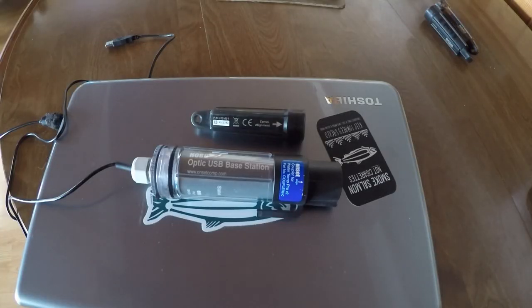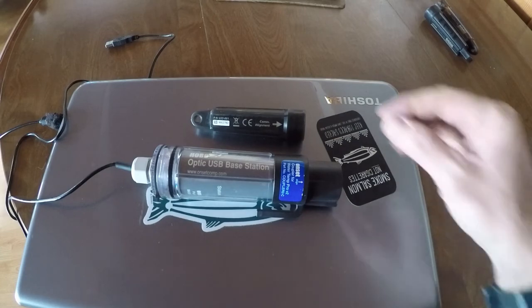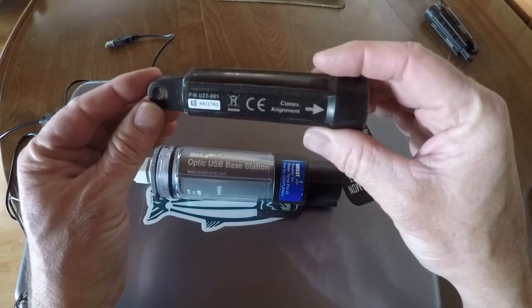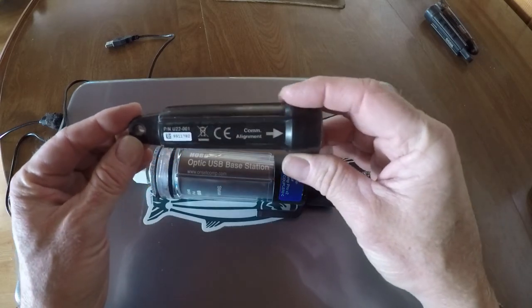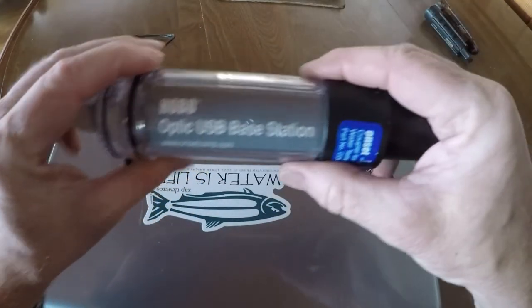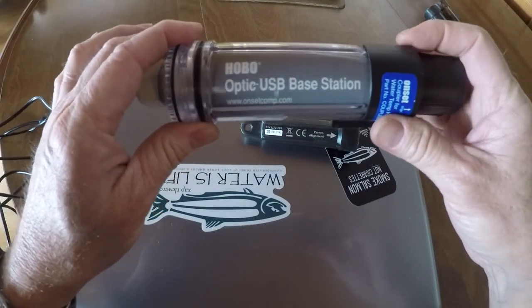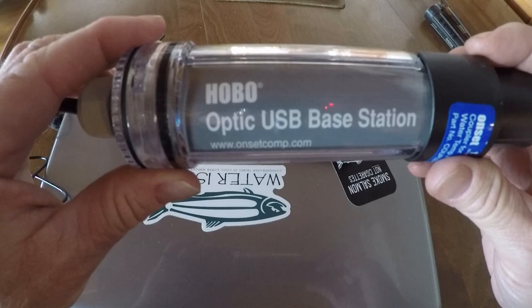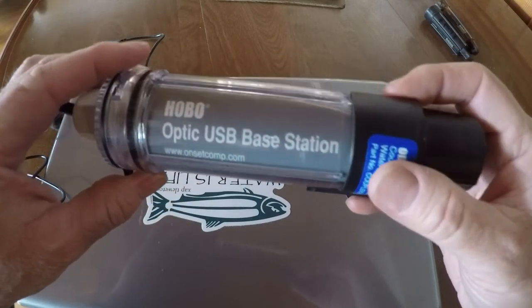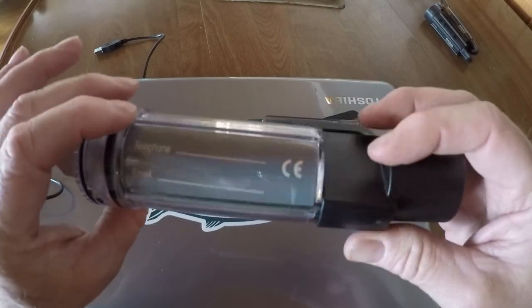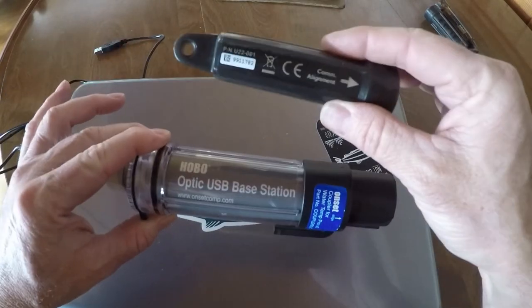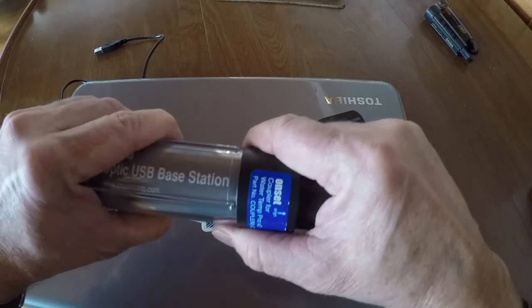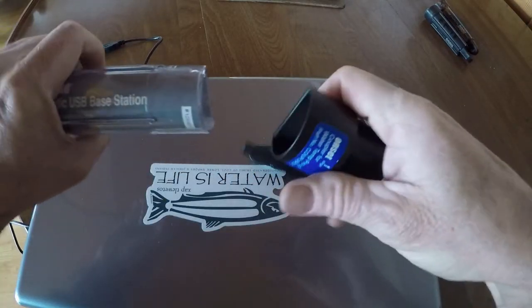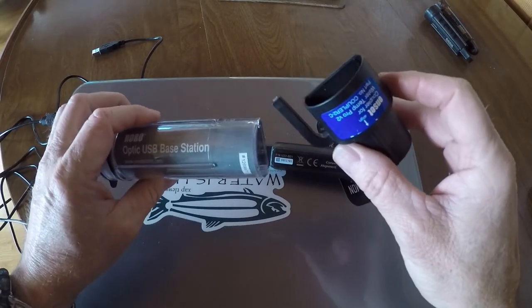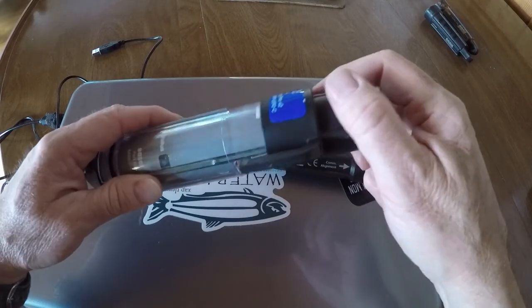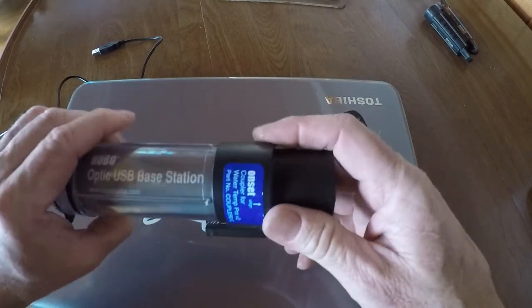Okay, so we've moved inside, and we're going to get the probe programmed to be able to perform our calibration tests. So the first thing to use is this HOBO optical USB base station, which is oftentimes just called a reader. And this can read more than just the particular one probe that we're using. It can do various ones. And so if you don't have that particular probe, you can find that this end piece actually comes off, and you're able to slide whatever one that actually fits your probe onto it.